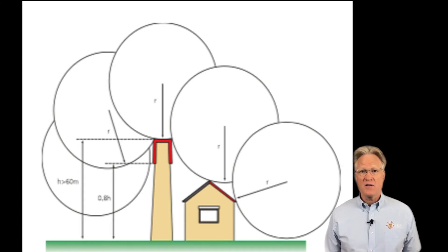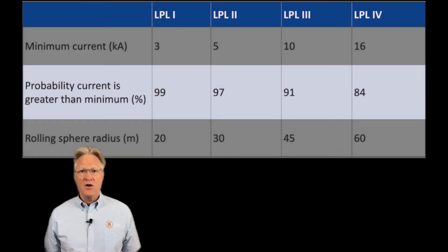The higher the protection, the smaller the sphere, and naturally the higher the cost of the system since more lightning rods are needed. Note the minimum current protected against. Each level of protection really has a range of protection and they don't start at zero.